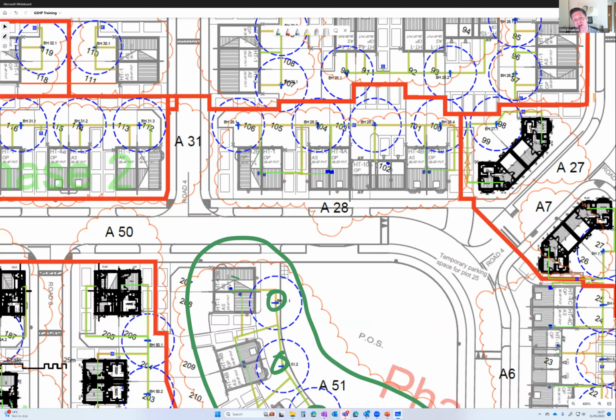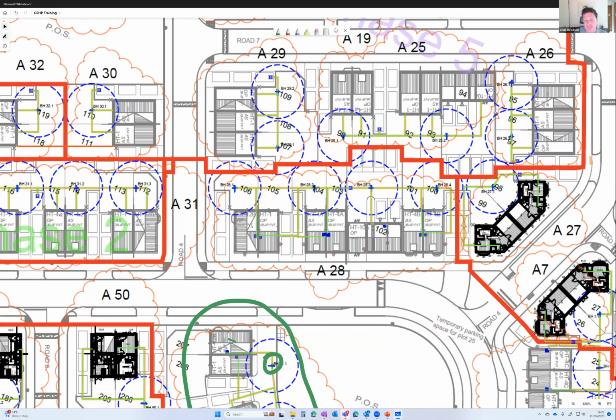Interestingly, if we look in a bit more detail up here, we've got array 28, which has 4 boreholes, and array 29 up top, which has a couple of boreholes. They are not in hydraulic contact, so there's no hydraulic connection between those two heat networks, but they are close enough together to be thermally interfering with each other.